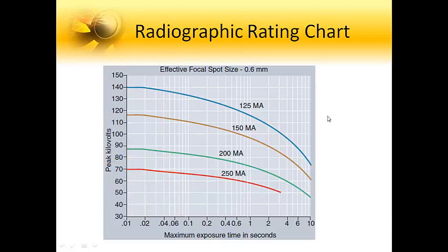For example, I want to check 60 kVp, with a time of 0.4 seconds, for 250 mA.